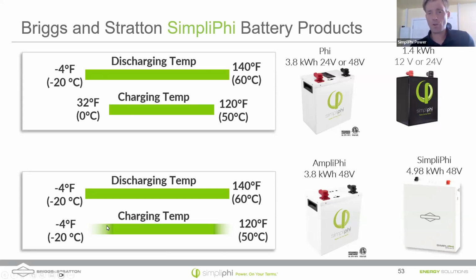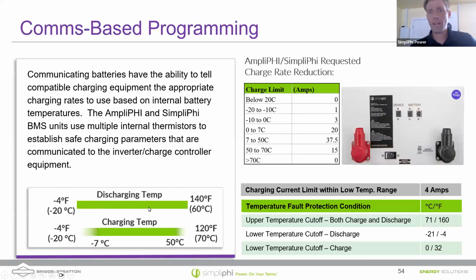And so their charging range on these batteries can go all the way down to negative 20 degrees Celsius, and up to 50 degrees Celsius on the charge cycle. The reason that the line is kind of blurred here at the lower side is we slow down that charging rate in cold temperatures. So this slide here, if you want the details off of it, you'll all be getting copies of these slides today.